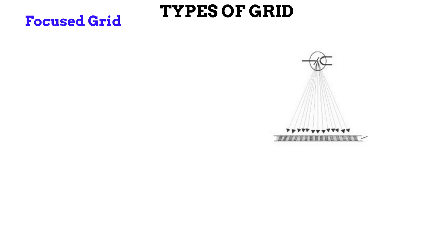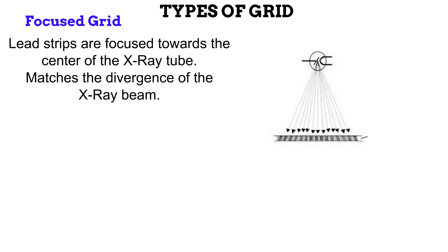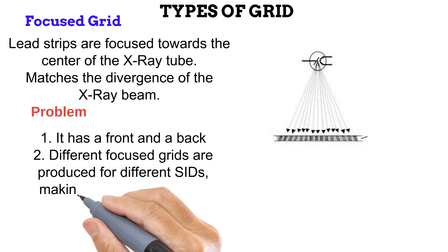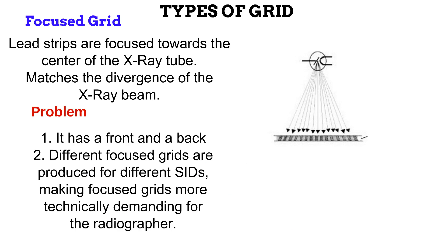The next type of grid is the focused grid. In this, the lead strips are not parallel to each other. Instead, they are tilted so that every lead strip is focused towards the center of the X-ray tube. This way, the divergence of the X-ray beam is matched, with less peripheral geometrical cutoff. However, focused grids have their problems. First, it has a front and a back, meaning the radiographer must pay extra attention to avoid placing it upside down. Secondly, different focused grids are made for different source-image distances, and if the wrong SID is used, geometric cutoff is produced. Using focused grids requires more carefulness and expertise than using parallel grids.